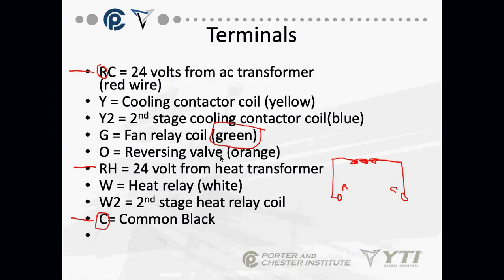Okay, so when you're drawing your diagrams, before you turn in diagrams, when you draw your ladder schematics using a low voltage side, just double check and make sure that there's absolutely no rung of your ladder that comes across from R to C without having a load in the center. Just eyeball it before you submit it, because that's a direct short circuit and you're going to burn out the transformer.